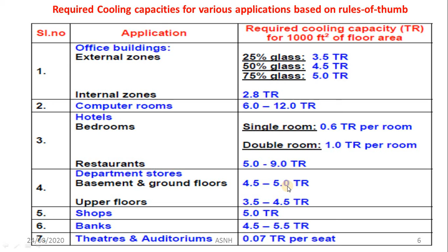Now, a more accurate load estimation method involves a combination of the analytical method and empirical results obtained from actual data. So we must consider the internal and external standard conditions. Suppose we are situated in the Pune area, then we must consider the internal and external conditions of that Pune area. So we must select the dry bulb temperature, wet bulb temperature, relative humidity, and specific volume corresponding to that Pune area only. If we are situated in the Mumbai area, then we must consider the standard conditions of that Mumbai area, okay, in order to calculate the heat load.